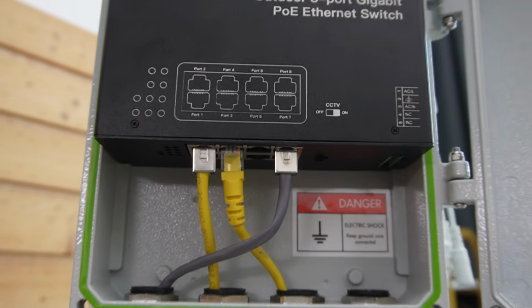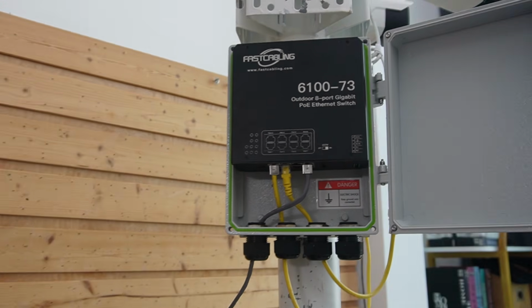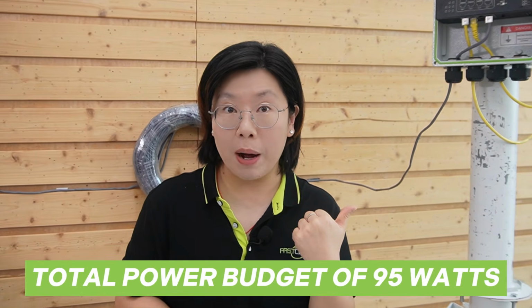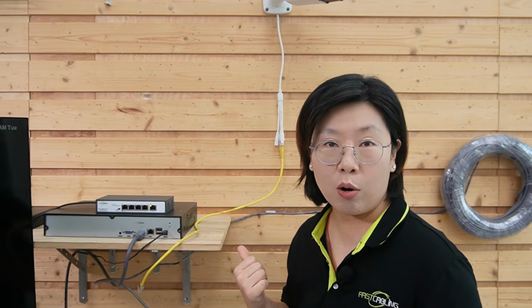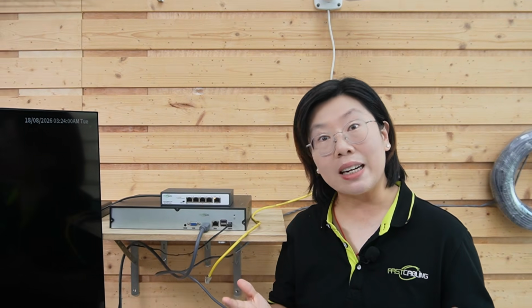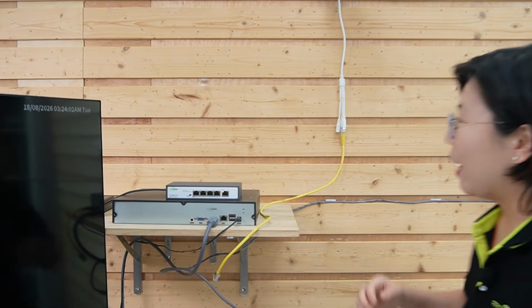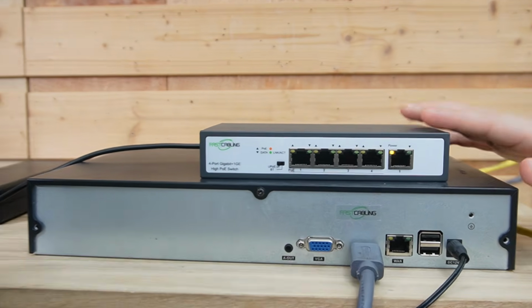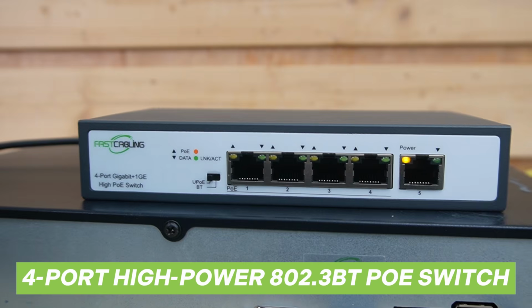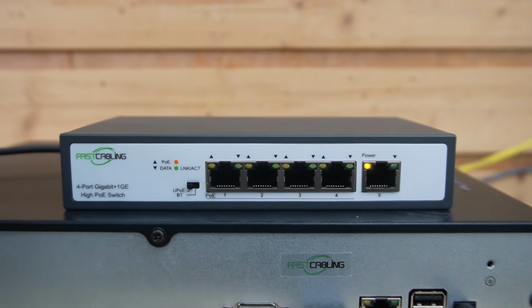Now here's the time when we have to think about power budget. This switch has a total power budget of 95 watts with up to 30 watts per port. But that power has to come from somewhere, and it's coming all the way from the control room through that single Ethernet cable, so we need a high power provider on the other end. That's why we are using this 4-port high-power 802.3 BT PoE switch in the control room.